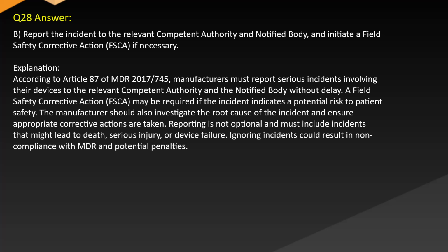The manufacturer should also investigate the root cause of the incident and ensure appropriate corrective actions are taken. Reporting is not optional and must include incidents that might lead to death, serious injury, or device failure. Ignoring incidents could result in non-compliance with MDR and potential penalties.